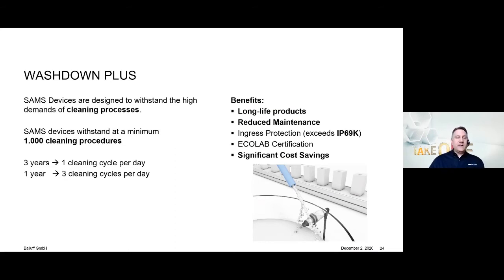What does that mean? It means the device is designed and guaranteed to withstand a minimum of 1,000 wash cycles. So if your cleaning cycle is 3 times a day, the device is designed to last a year. If it's once a day, it's designed to last 3 years at a minimum. So now we're addressing being able to last longer, and as we talk about the feature set, you'll see we can identify or predict when the device would fail before it does, so you can replace it on your time, not when it decides to fail on its own.